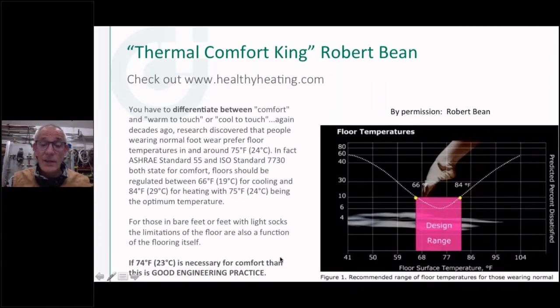So that's another little thing to do if you want a really nice consistent floor temperature, is get that spacing tighter, get it down to a 9-inch, even a 6-inch if you can do it, because that's going to even out that surface temperature, and it's going to allow you to run that slab at a lower supply water temperature to get that amount of output, because now I've got the whole entire slab at a consistent temperature instead of having that what we call striping, where you got warm over the tube, cool spaces in between it.